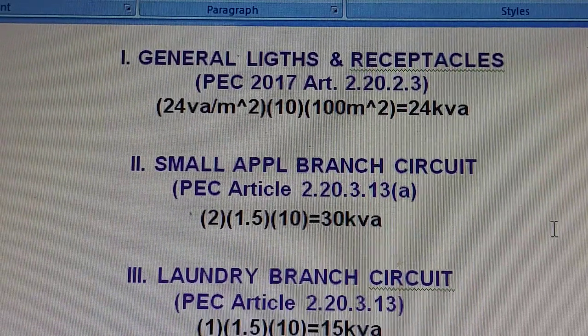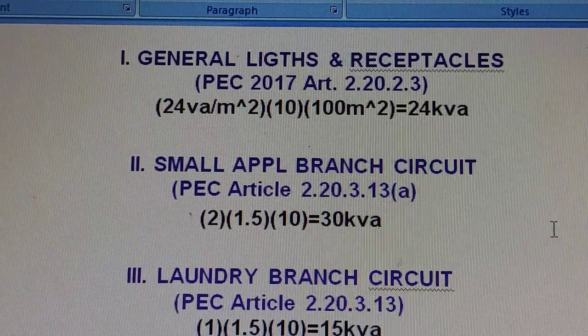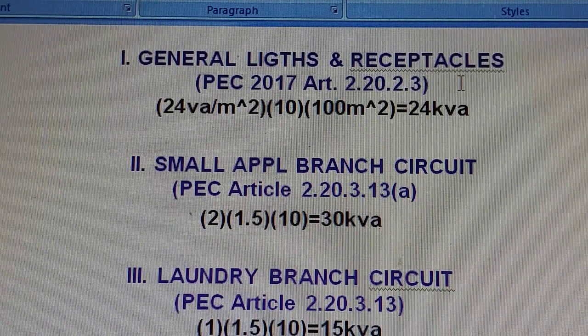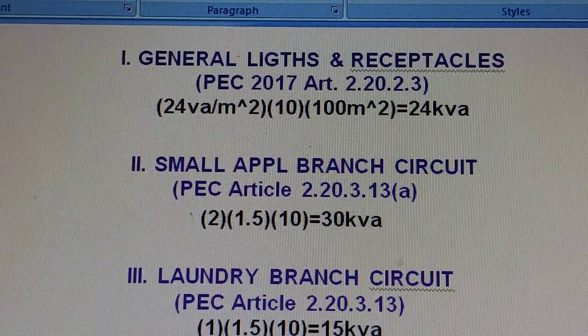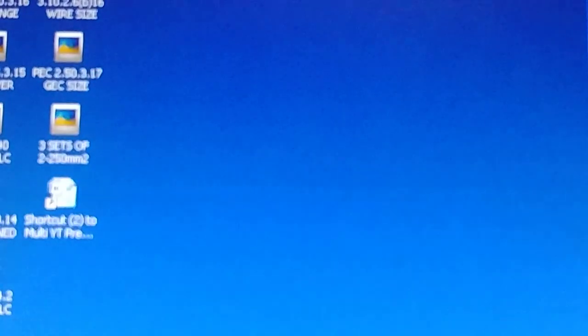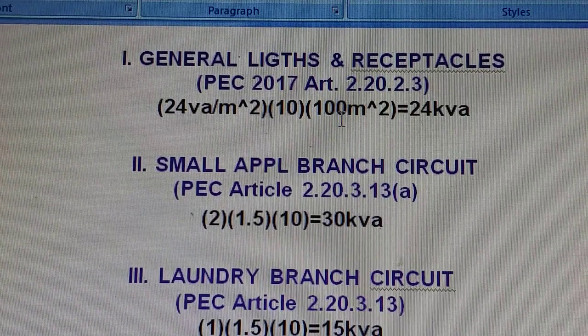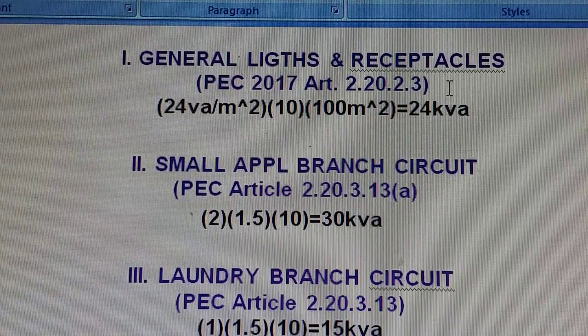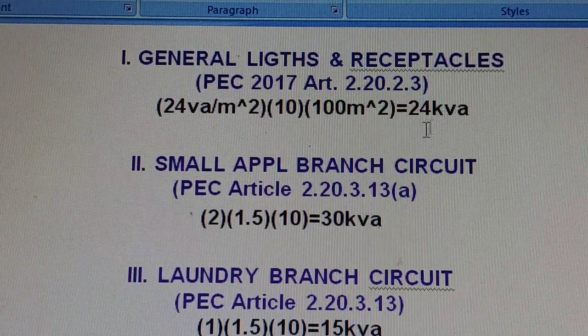For the general lights and receptacles, let's refer to PEC 2017 Article 2.20.2.3. In this article, under dwelling unit types of occupancy, we have 24 VA per meter squared for the unit load. So we have 24 VA — this is a dwelling unit based on this article — times 10 units times 100 square meters, which equals 24 kVA. We use the area method here for this calculation.